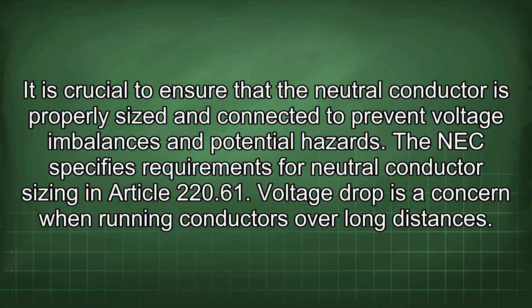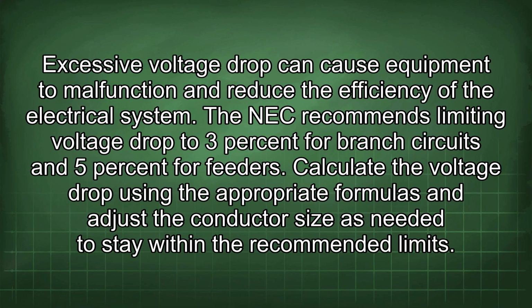Voltage drop is a concern when running conductors over long distances. Excessive voltage drop can cause equipment to malfunction and reduce the efficiency of the electrical system. The NEC recommends limiting voltage drop to 3% for branch circuits and 5% for feeders. Calculate the voltage drop using the appropriate formulas and adjust the conductor size as needed to stay within the recommended limits.